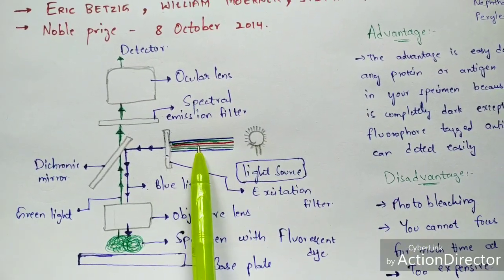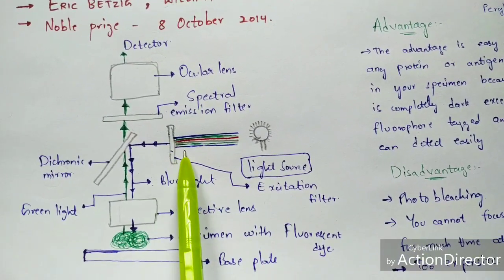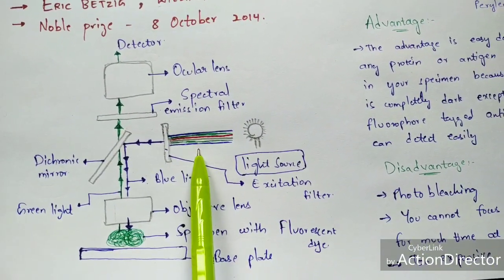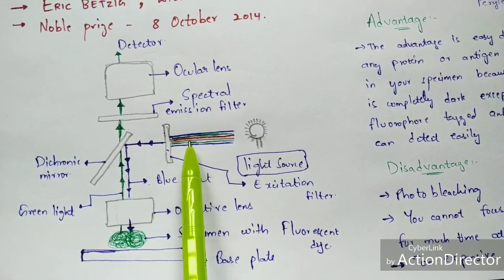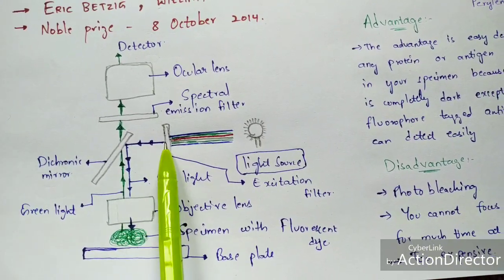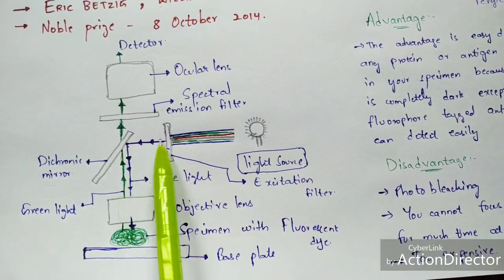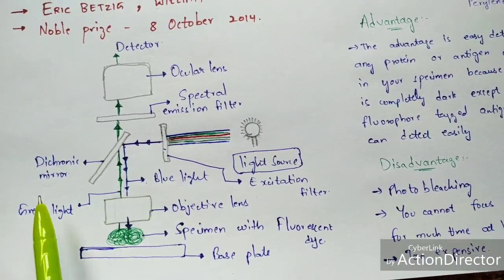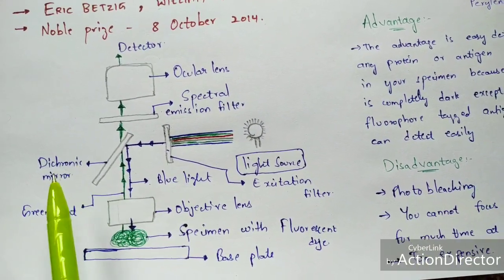From the light source, light is emitted and falls upon the excitation filter. Since light consists of different colors, the excitation filter selects a suitable wavelength and allows only blue color light to be emitted out. This blue color light is then allowed to fall upon the dichroic mirror.